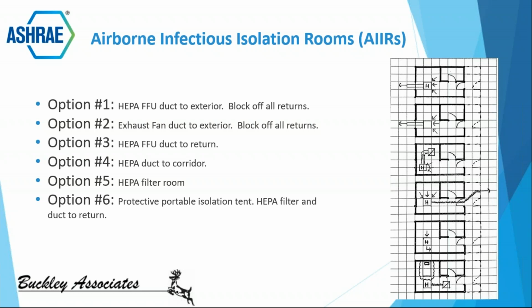Now it's important to note in this scenario that all returns in the space basically need to be blocked off to ensure that the room is going to be negative, because the air is going to come from somewhere. And if we block this off, that's the only way we're going to maintain proper filtration and negative pressurization in the room. Now, option 2 that they laid out is very similar to option 1. They're still recommending this solution over the rest of them without HEPA filtration. Obviously, we want to HEPA filter this virus, but it's more important to get it out of the space and maintain negative pressurization than anything else.